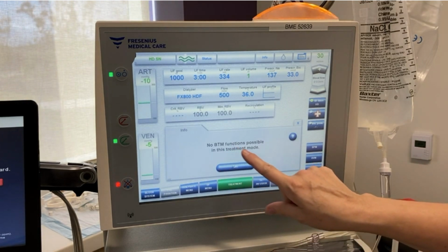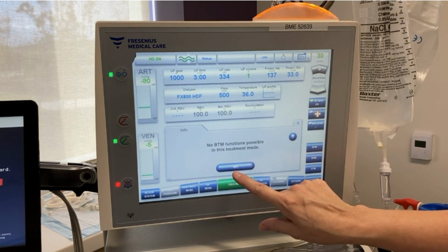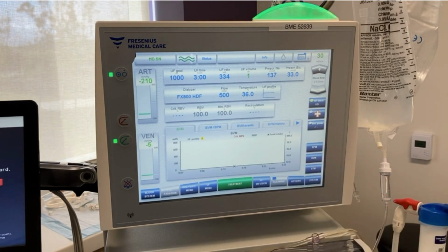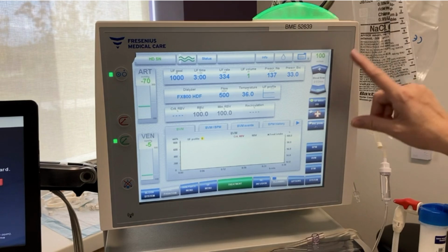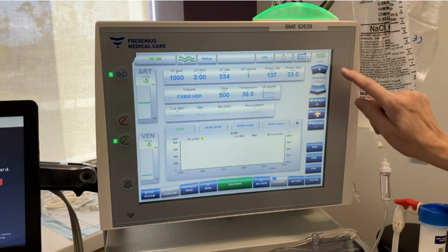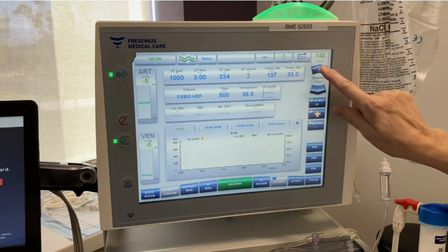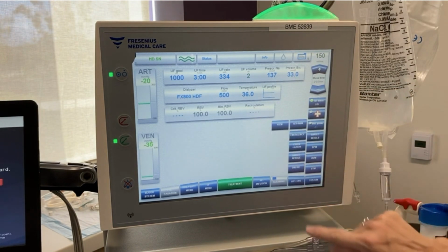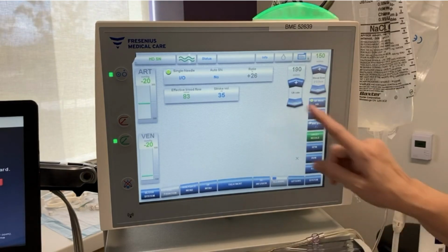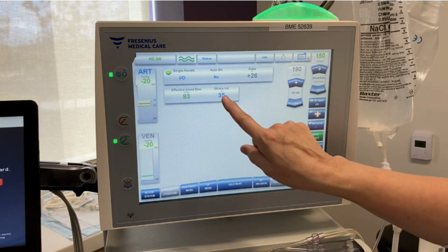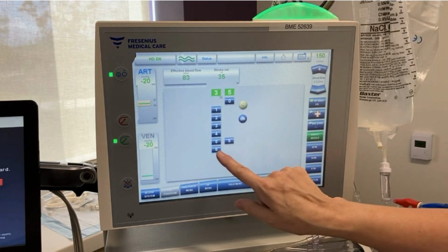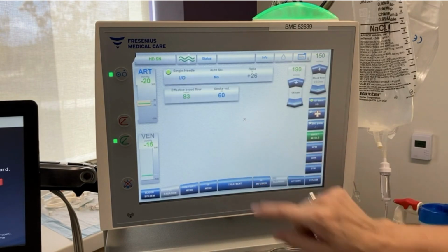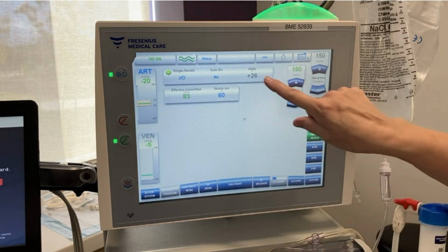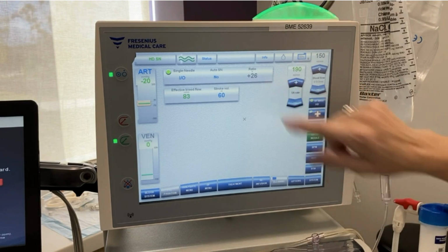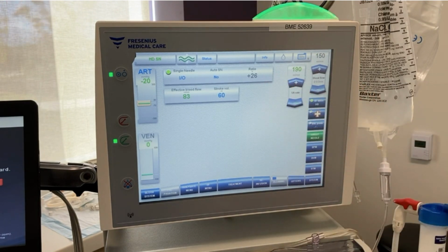I can't use the BTM functions in this treatment mode, so I'll just say okay. And now our pump speed is at 100. I'm just going to increase it to 150. Then I'm going to go to options and choose single needle. Going to single needle, my stroke volume is at a default of 35, and I'm going to increase that to 60.